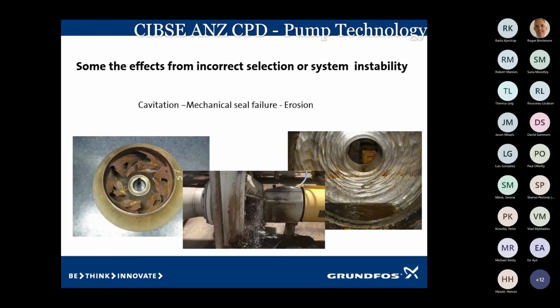This is a couple of shots here. You can see the one on the left is cavitation. We'll talk about cavitation soon. And that's the suction port of the impeller. And you can see what's left of the vanes. The cavitation has drilled into those impeller vanes and really destroyed it. That's how much is happening inside that pump. There's so much turbulence going on when it's cavitating.